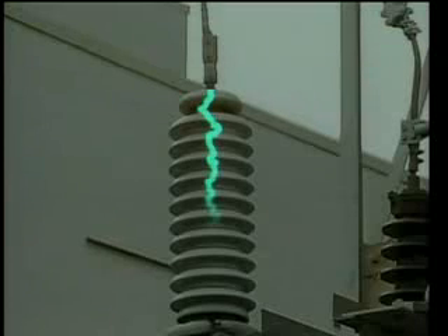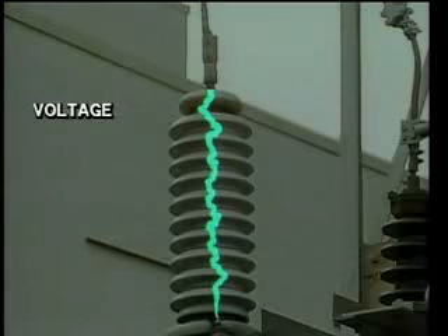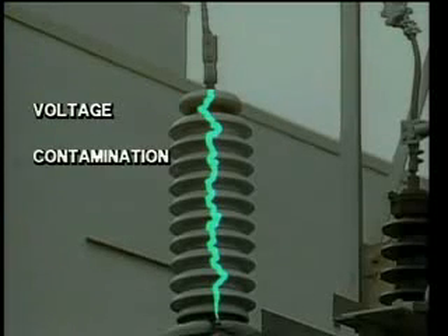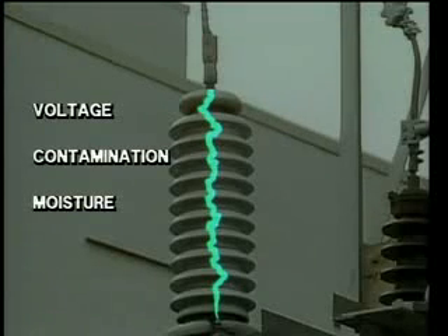Tracking is discharges of current across the surface of an insulated terminal. Tracking can result when three conditions are present. These are voltage on the conductor, contamination on the termination, such as dust, chemicals, or salt, and moisture on the termination, such as moisture from humidity, fog, condensation, and rain.